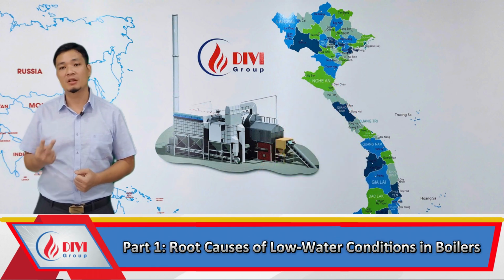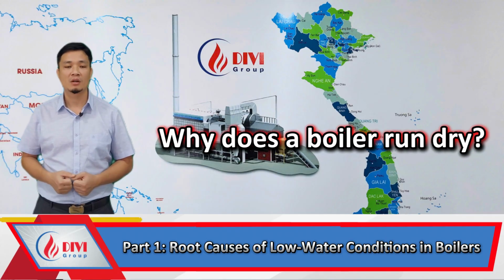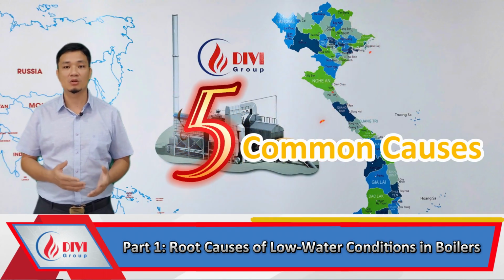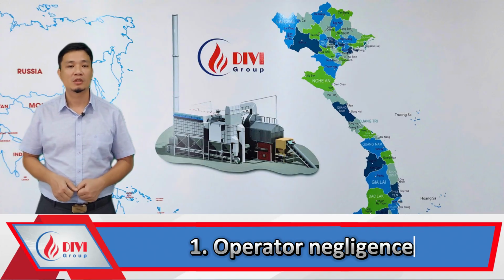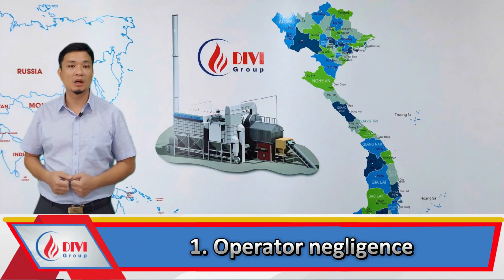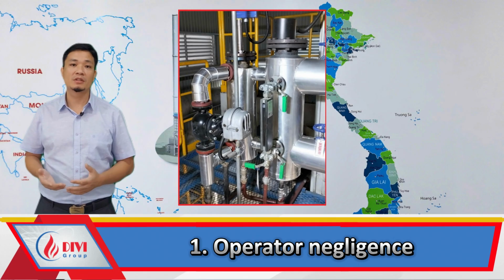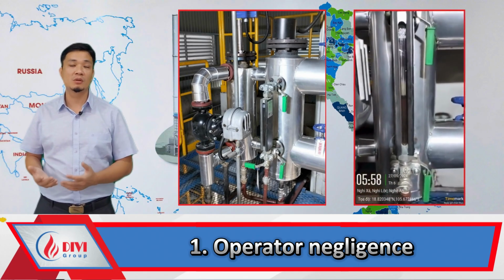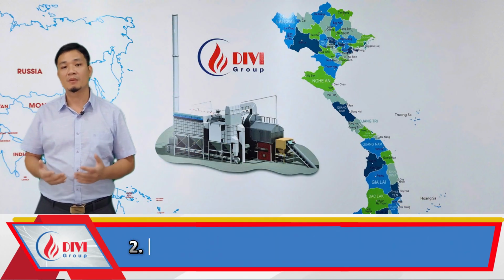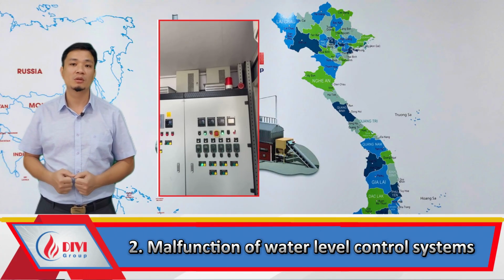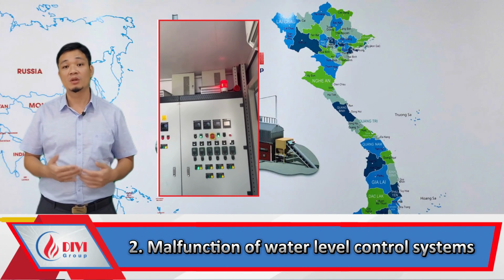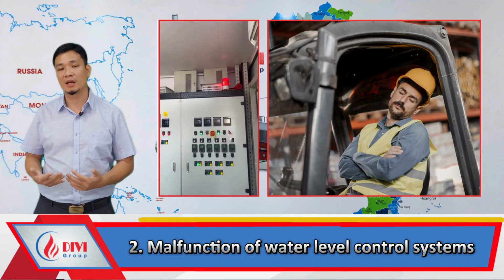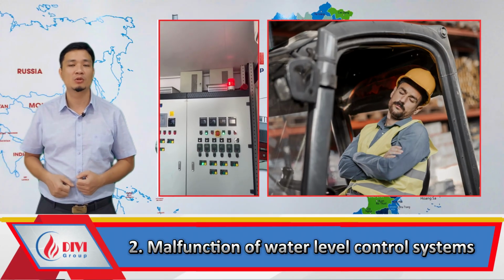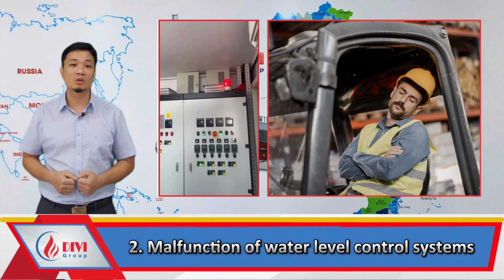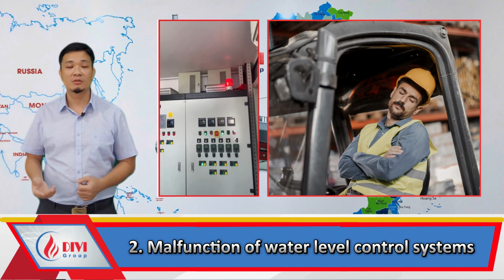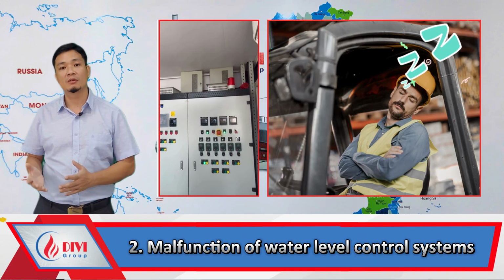Part 1, root causes of a boiler dryout condition. Here are the 5 most common causes of severe low water level. Operator negligence: infrequent or improper monitoring of the water level indicator, sight glass, misreading water level due to poor visibility or lighting, possibly due to operator absence or falling asleep during the shift. Malfunction of water level control systems: faulty level sensors, failed alarm systems, malfunctioning modulating control valves, leaking or jammed check valves causing unnoticed water loss.